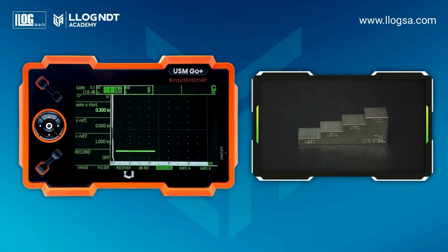When only one reference is available and the component to be inspected is thicker than that reference, we can perform calibration using multiple echoes. We will use the same initial settings as in the previous calibration, but this time, using only the 1 inch thickness of the block as our reference. In the Auto Calibration menu, enter the known thickness value as reference 1. For this example, 1 inch. For reference 2, enter the value of the second ultrasonic path, 2 inches.